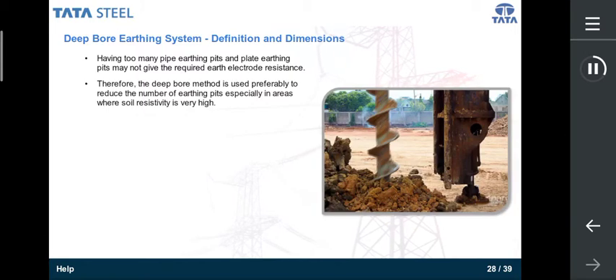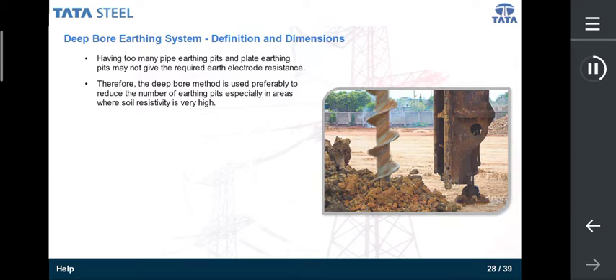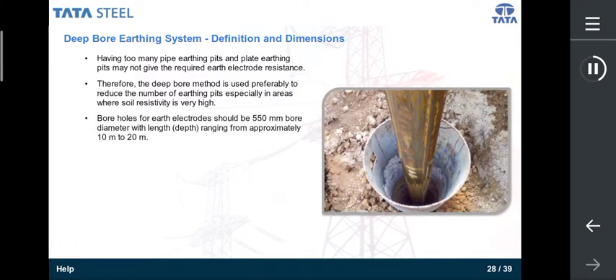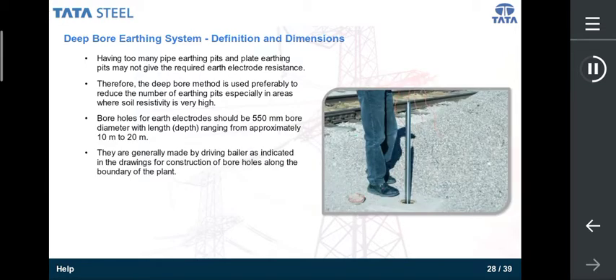Therefore, the deep bore method is used preferably to reduce the number of earthing pits, especially in areas where soil resistivity is very high. Let us now look at the dimensions required for deep bore earthing. Bore holes for earth electrodes should be 550 mm bore diameter with length or depth ranging from approximately 10 meters to 20 meters. They are generally made by driving bailer as indicated in the drawings for construction of bore holes along the boundary of the plant.